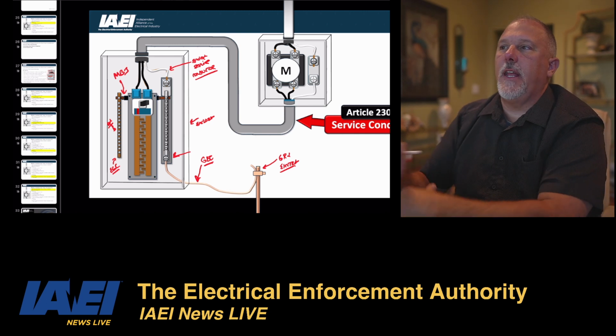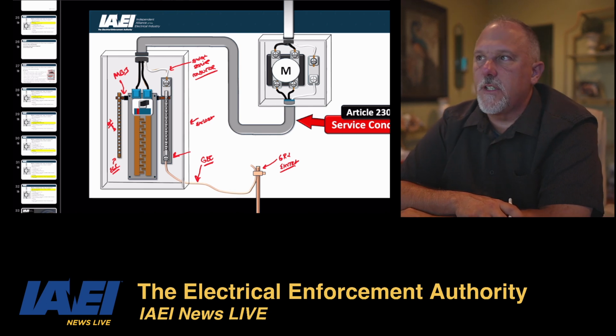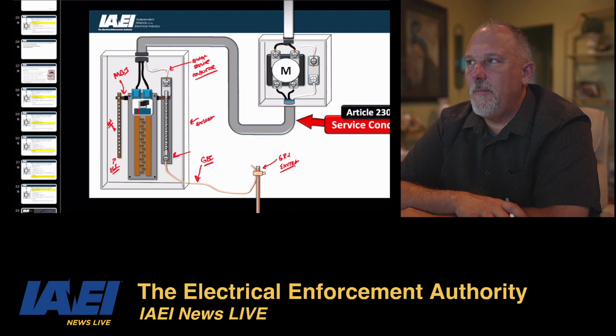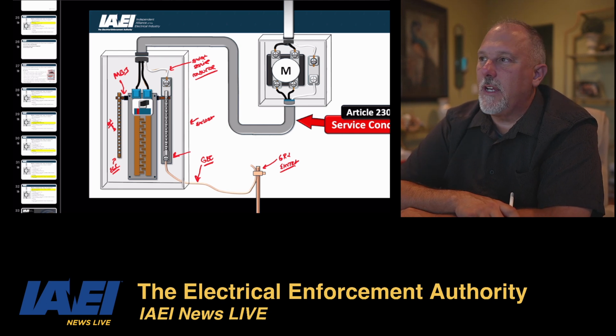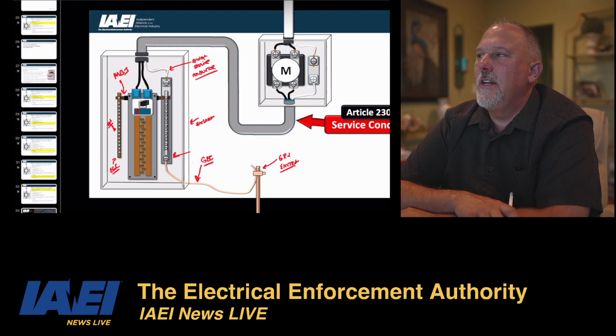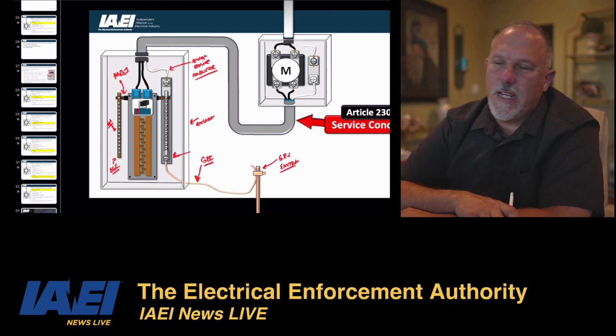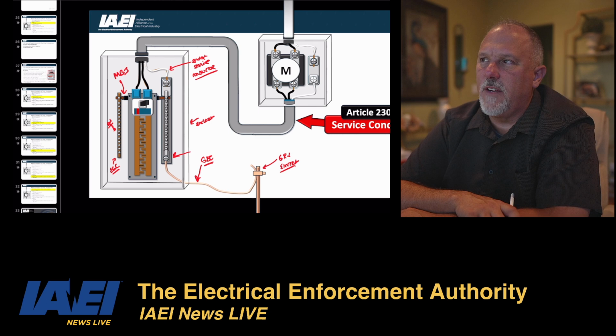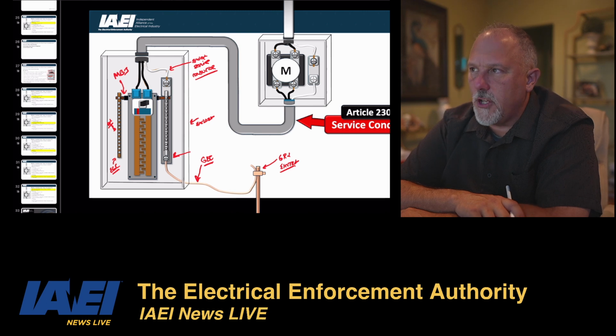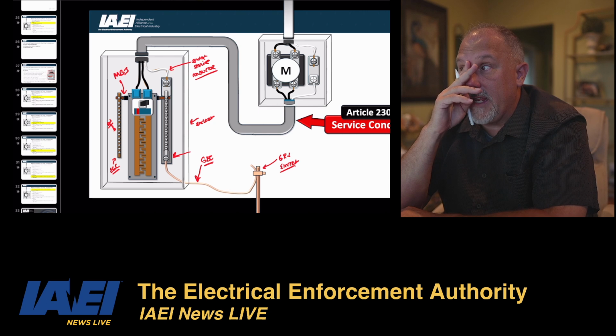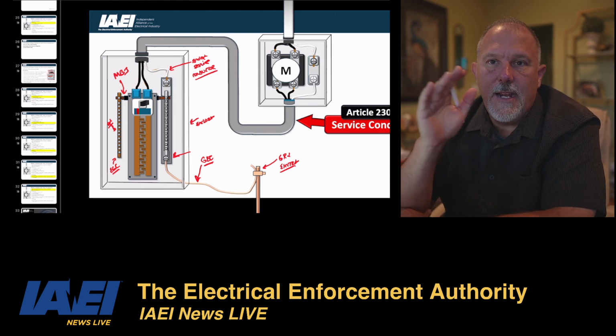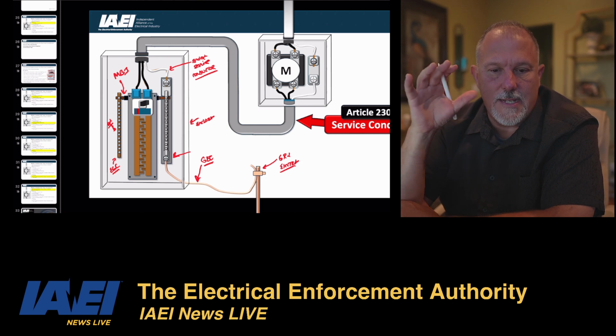250.92 talks about the bonding of equipment for services. The normally non-current-carrying metal parts of equipment indicated in the following. So all raceways, cables, cable trays, cable bus framework, auxiliary gutters, etc. To take a look at 250.92(A), bonding of equipment for services, they all have to be bonded together. All enclosures containing service conductors, including meter fittings, boxes, and the like. So just think, anything that's metal has to be all bonded together.